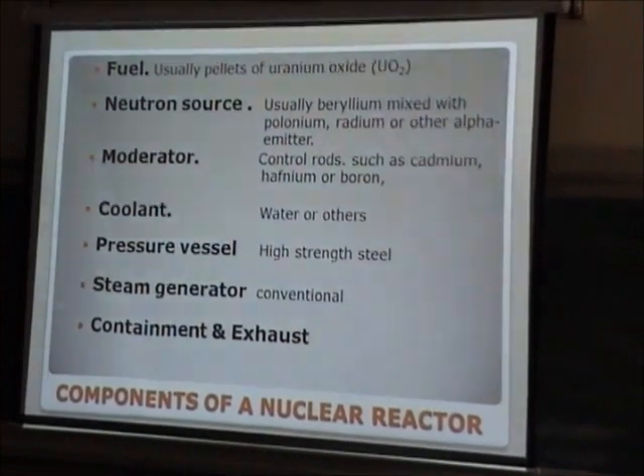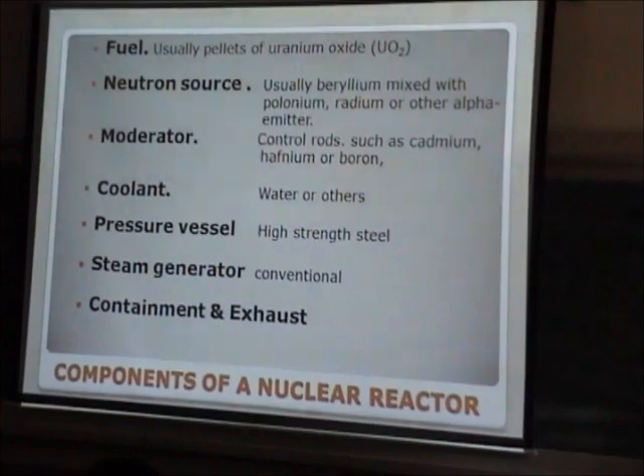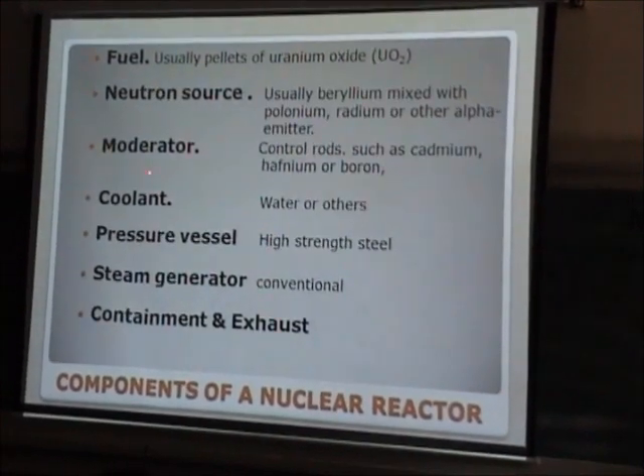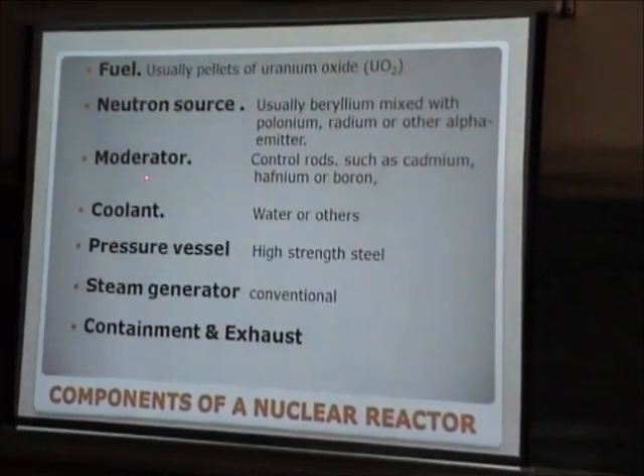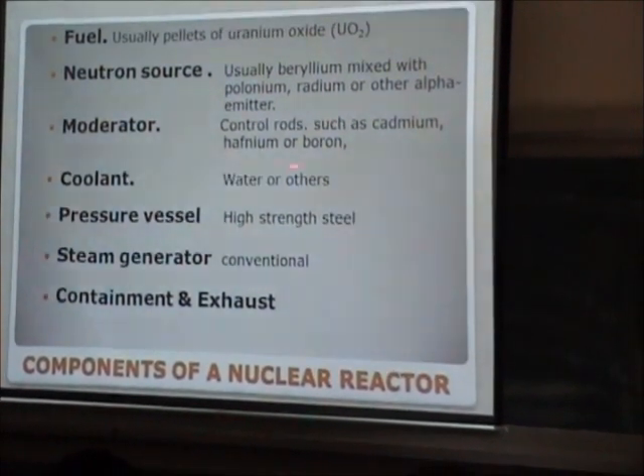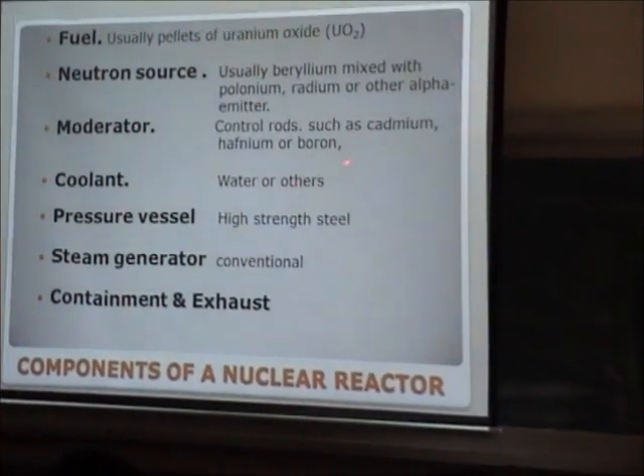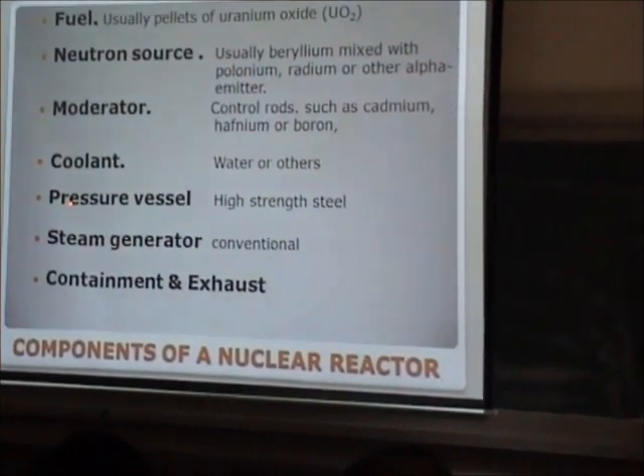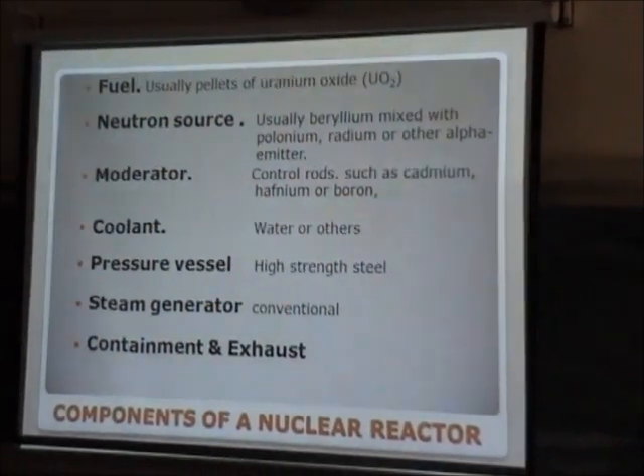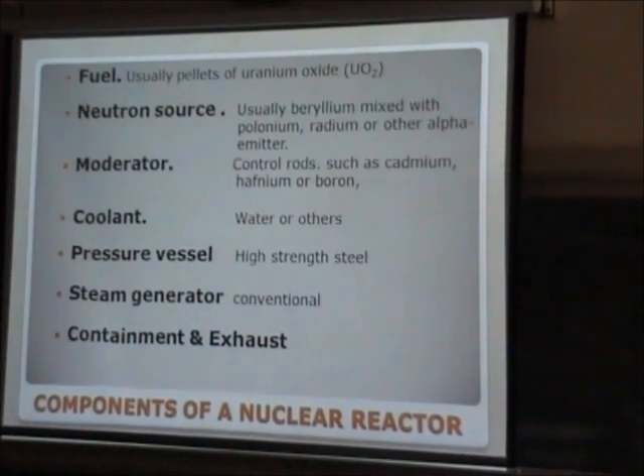The neutron source is usually beryllium combined with polonium, radium, or other alpha emitters, which starts the fission process in the reactor. A moderator is also used — like heavy water or graphite — to moderate the neutrons. Then a coolant is used to carry away the heat, such as light water, heavy water, or other materials. We also have the pressure vessel which houses the reactor for safety, and then the conventional steam generator and containment.